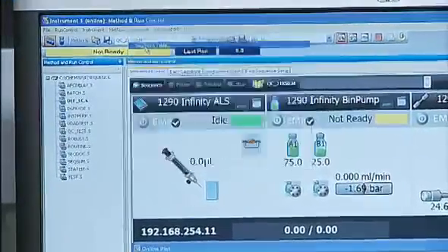We can also remove the autosampler source of ghost peaks by making a run without any involvement of the autosampler. We sometimes call this a blank gradient. That is, we start the gradient without any action by the autosampler, including there's no valve switching. With ChemStation, if you do not set a vial location in the sequence table, the entire autosampler operation is skipped.